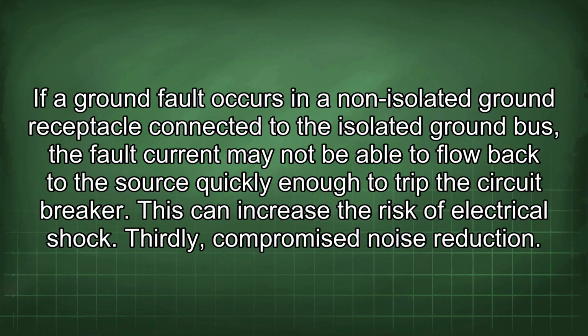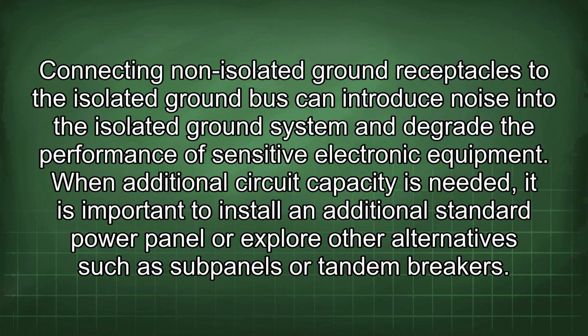If a ground fault occurs in a non-isolated ground receptacle connected to the isolated ground bus, the fault current may not be able to flow back to the source quickly enough to trip the circuit breaker. This can increase the risk of electrical shock. Thirdly, compromised noise reduction. Connecting non-isolated ground receptacles to the isolated ground bus can introduce noise into the isolated ground system and degrade the performance of sensitive electronic equipment.